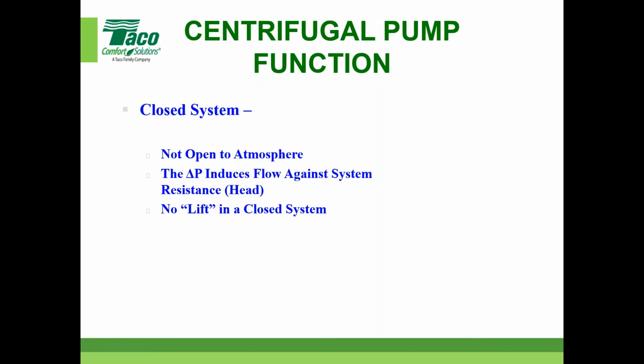There is no lift. The height of the building comes into play for pressures, length of pipe, and volumes, but the height doesn't necessarily add a calculation to the system resistance. Sometimes people ask how that comes into play—you've got to calculate all the twists, turns, and elbows, but there's no lift per se in a closed loop system. And again, that's most of the systems these HVAC pumps are installed in for the most part.